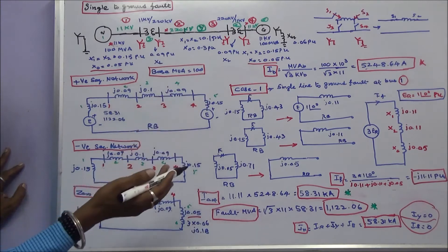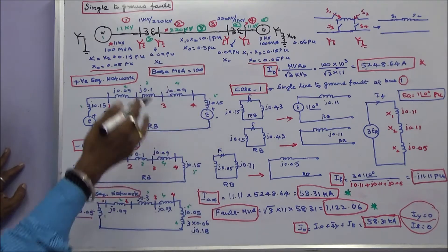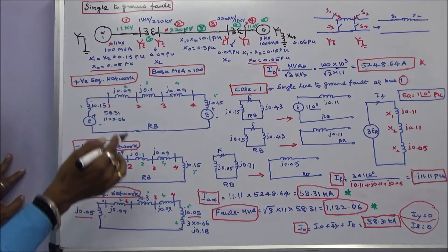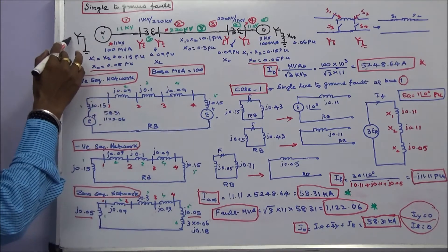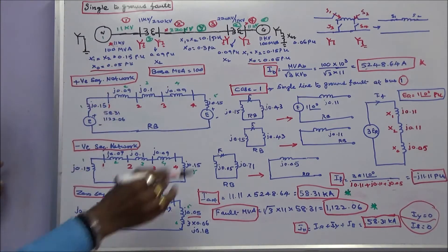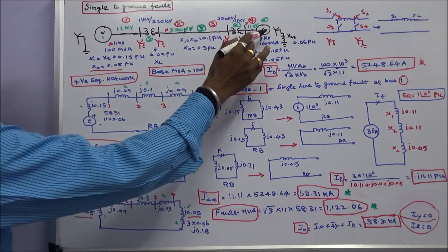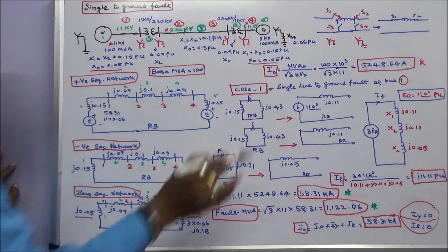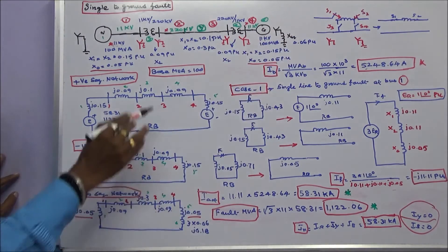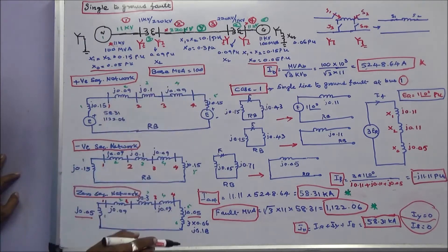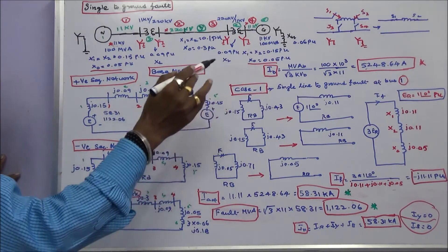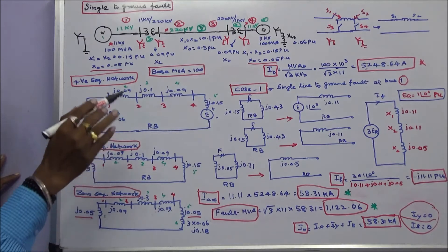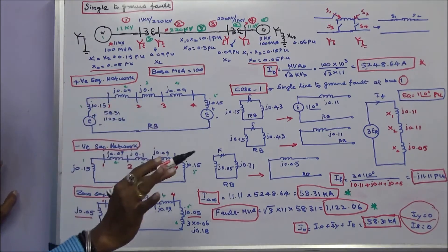This last problem uses the same data as in the first problem. Generator 1 is a star-connected machine with neutral grounded. Generator 2 is a star-connected machine with neutral grounded through a reactance of 0.06 per unit. Base MVA is equal to 100. Case 1: if a single line-to-ground fault occurs at bus 1, calculate the fault current and fault MVA.